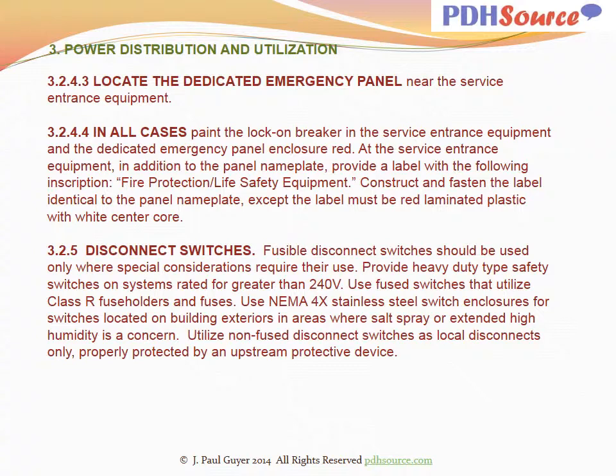Fusible disconnect switches should be used only where special considerations require their use. Provide heavy-duty type safety switches on systems rated for greater than 240 volts. Use fused switches that utilize Class R fuse holders and fuses. Use NEMA 4X stainless steel switch enclosures for switches located on building exteriors in areas where salt spray or extended high humidity is a concern. Utilize non-fused disconnect switches as local disconnects only, properly protected by an upstream protective device.